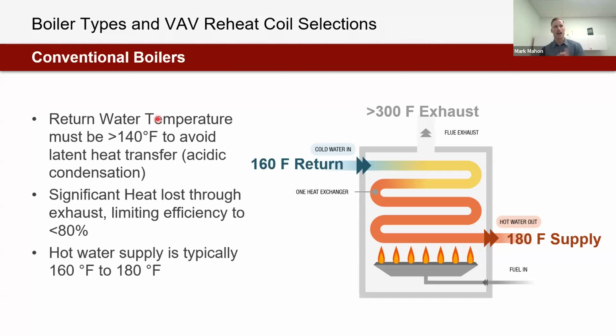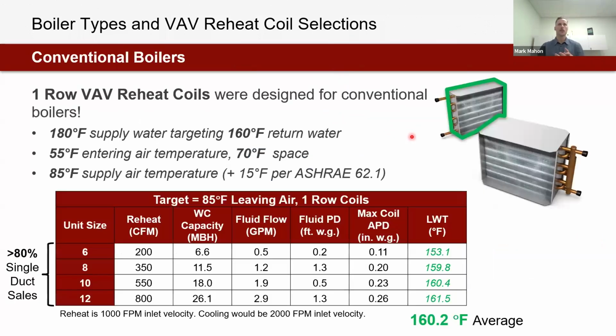Now, the outcome of this type of boiler is a COP limit of 0.8 or 80% efficiency. And I think a great proxy for that is our exhaust air temperature. These boilers have generally a very hot exhaust above 300 degrees Fahrenheit at design day. And so what we're going to see is with hot exhaust, we see a limit of COP and we see energy kind of lost to the environment in that case.